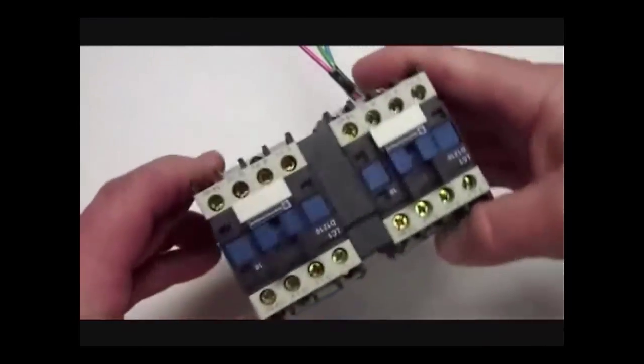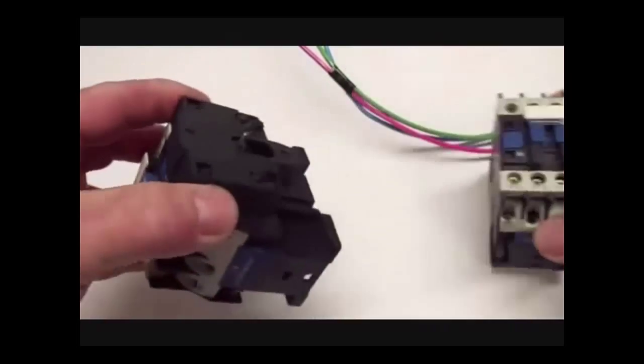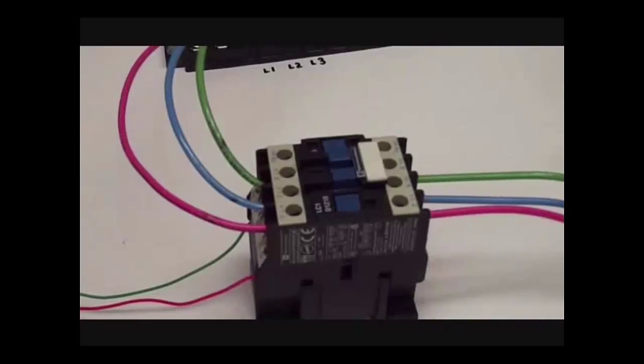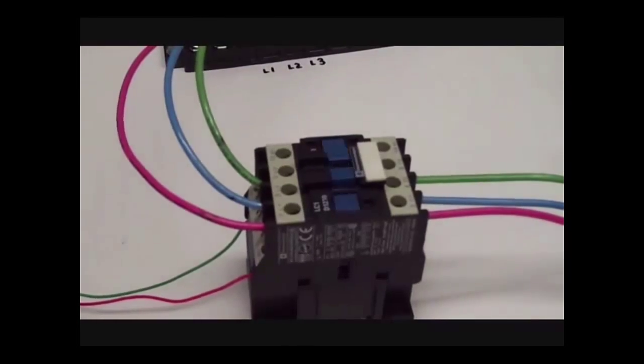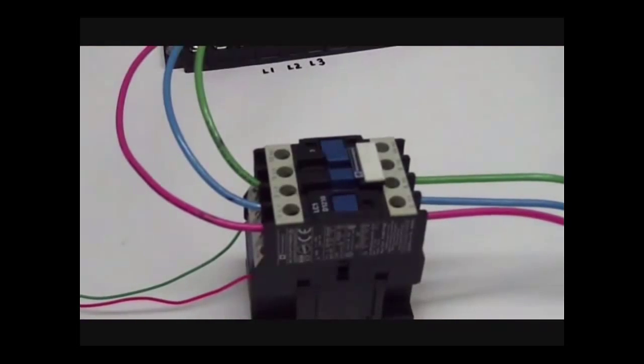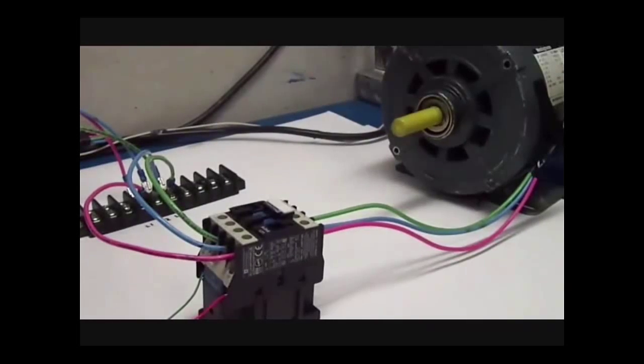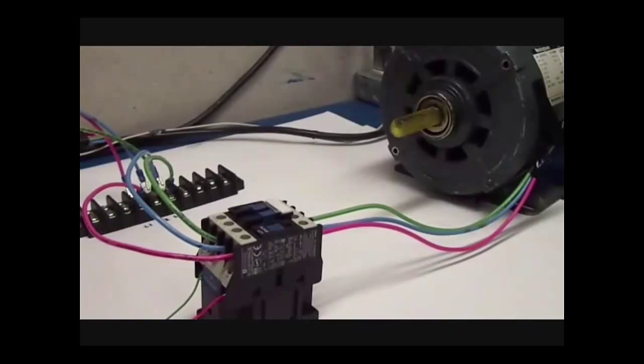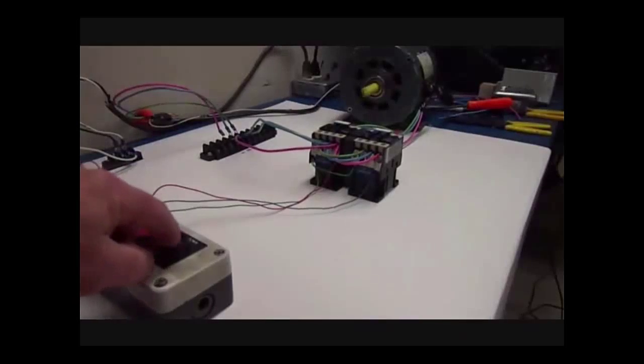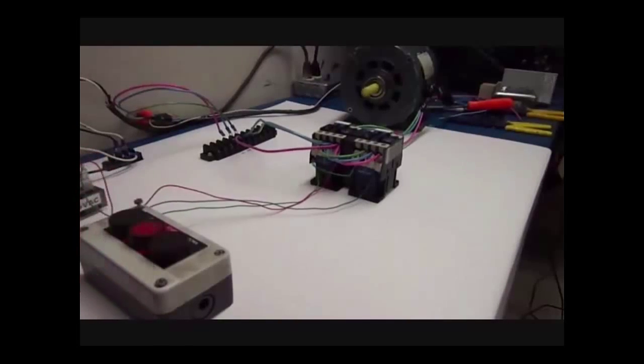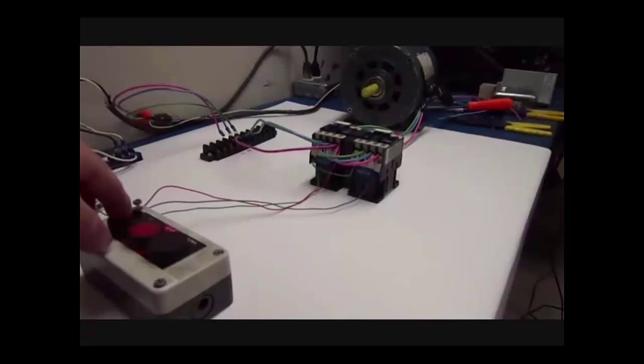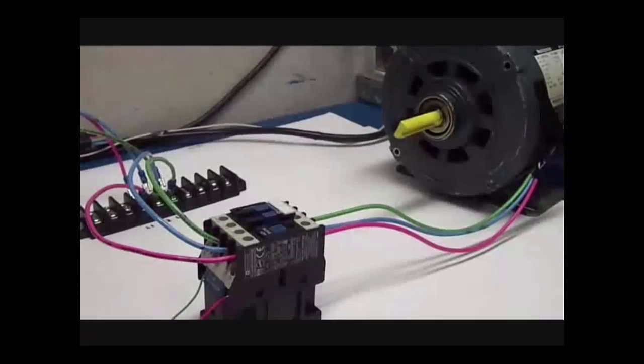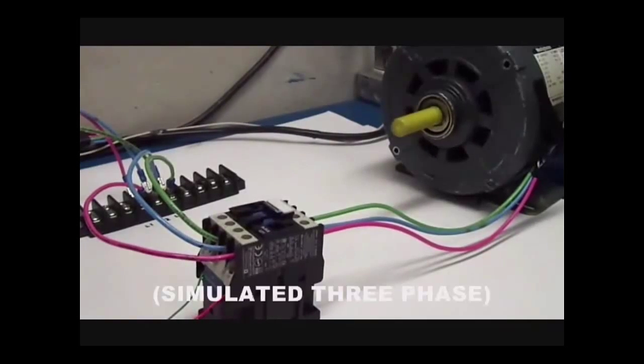So here's a more modern contactor with 2 coils and 2 sets of contacts. This one side with 1 coil is a contactor. This is what you would have for a motor that only needs to run in one direction, like a compressor. 2 contactors joined together with an interlocking device make this a reversing contactor for motors that need to run in both directions. Right now we're just going to use one side of it to run this 3-phase induction motor in one direction.